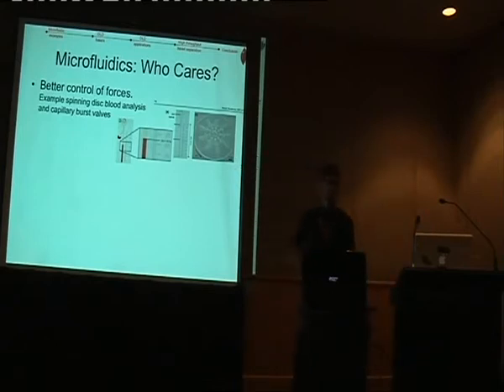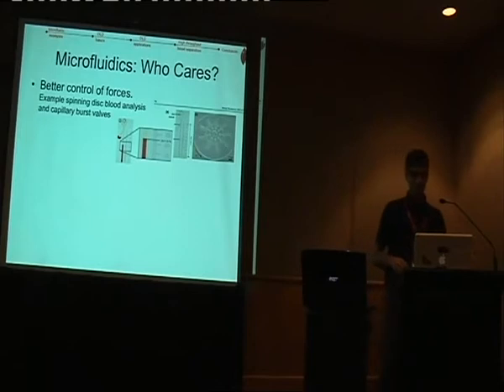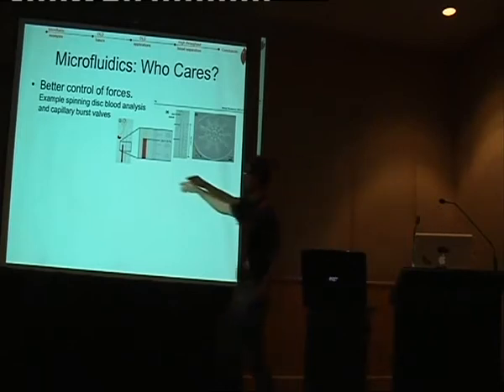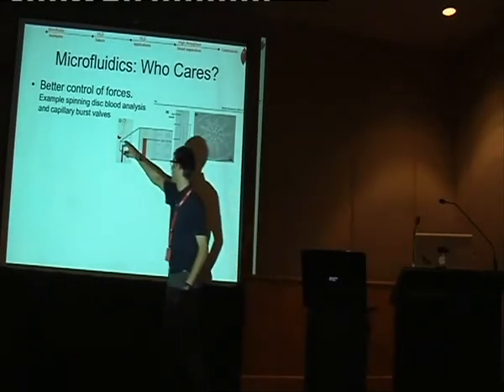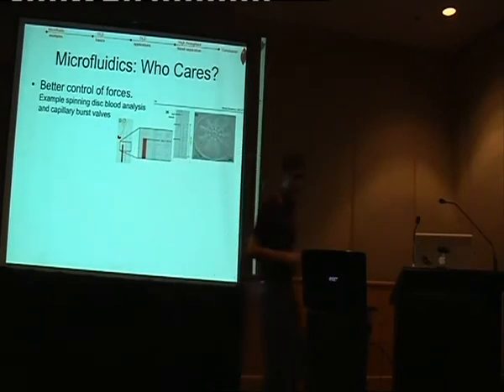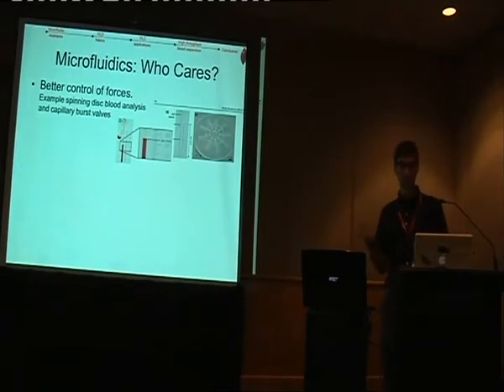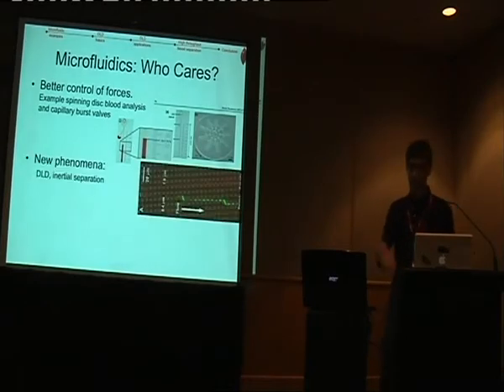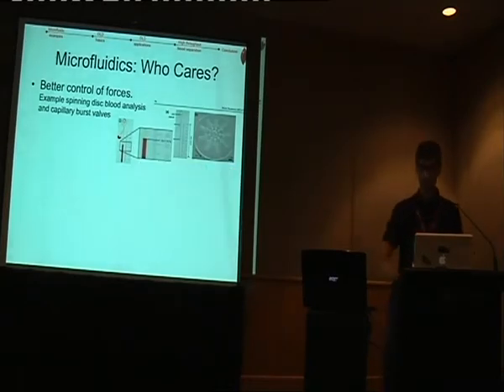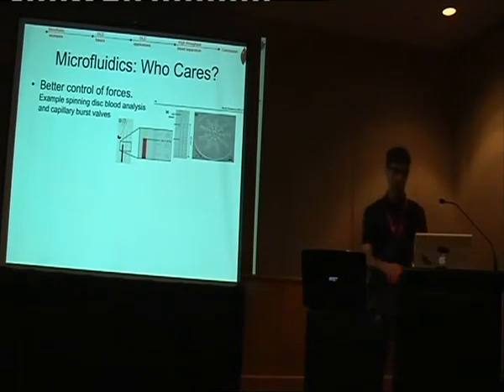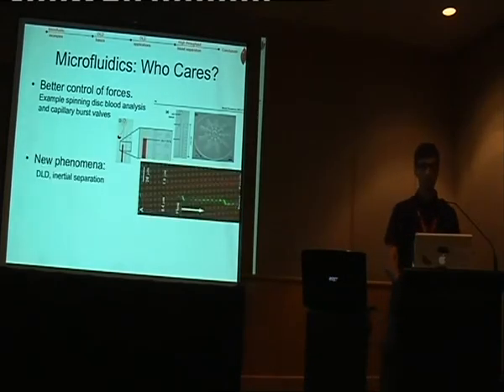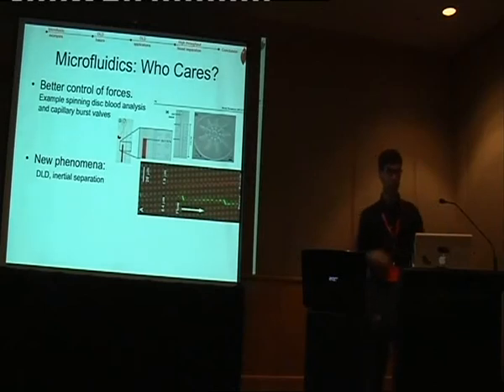And using something called a capillary burst valve, where you pattern a region of hydrophobicity, the fluid won't go through that until it reaches a certain RPM. So you can use that to meter around a certain volume of blood, and then you can just read off the hematocrit after you spin down the cells. It's not that different from what you do in a capillary tube. It's an example of the kind of control over forces you get.